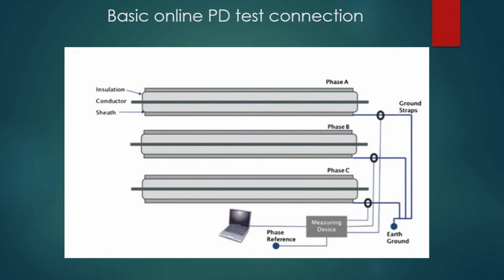Offline PD measurement is performed before installing cables into switchgear or transformers. Online measurement means the cable is loaded and in working condition. In the online setup, we can see the insulation, the conductor in the middle, and the cable sheaths for phases A, B, and C. Three clamps are joined to the three phases, connected to measuring devices, with earthing for the three phases going through the measurement device, and a phase reference connection leading to the PD analyzer.